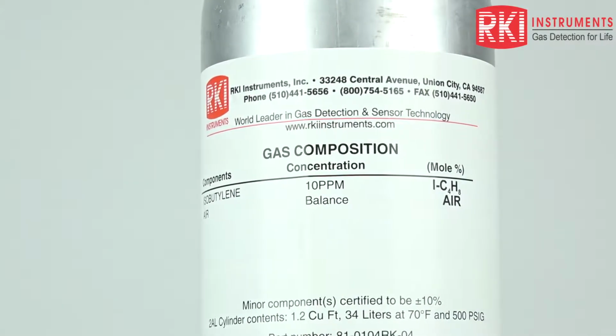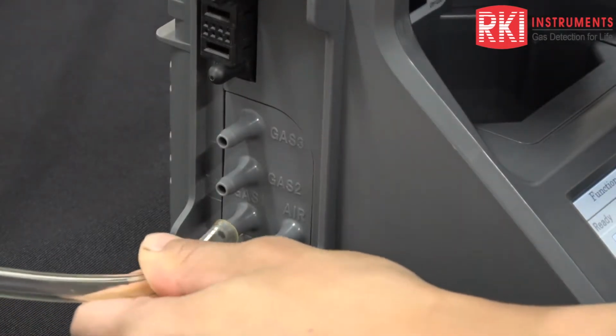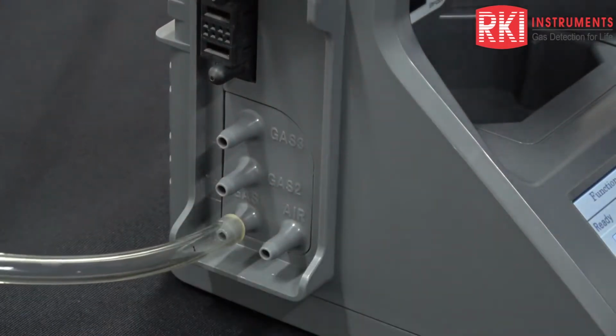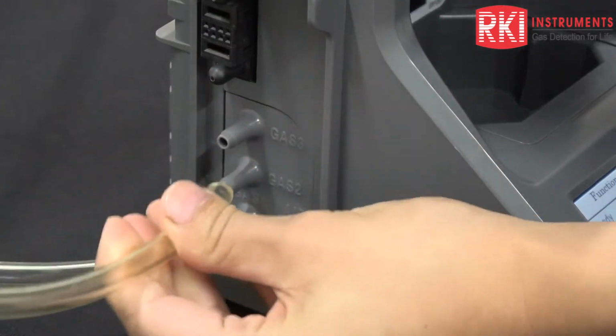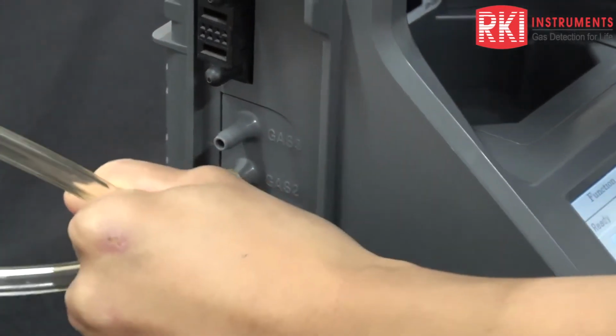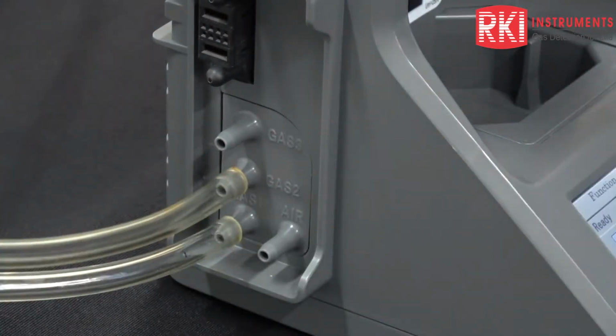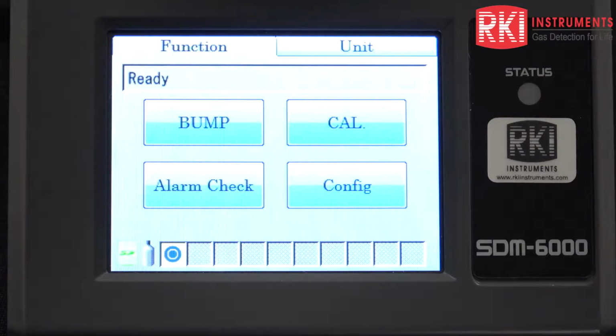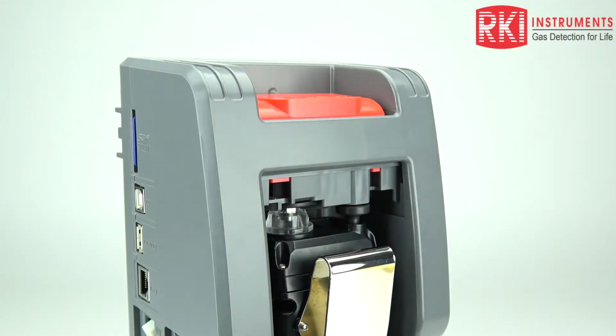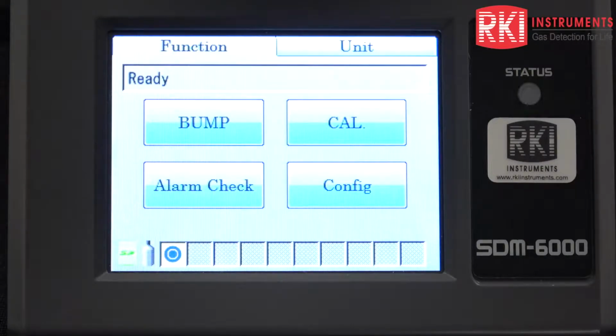Now I'm going to put gas 1 inlet into the 4-gas mix cylinder. And I'm going to set up gas 2 as isobutylene. So physically, I'm going to put in the gas inlets into the meter. So right now, I have the GX6000 plugged in with the red button pushed. That way it recognizes what sensors are in the 6000. And when we configure it, it's going to show up in the options. I have my gas 1 with the 4-gas mix cylinder and gas 2 with the isobutylene cylinder.